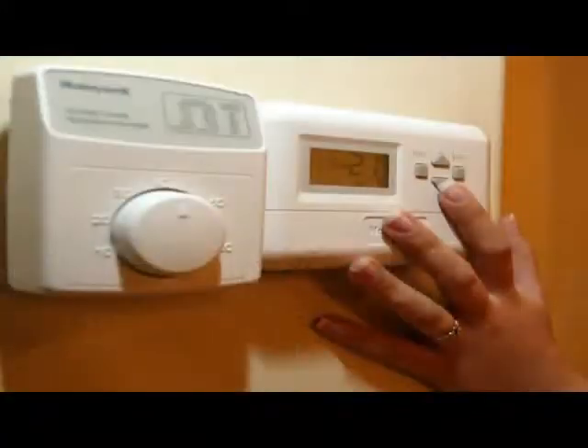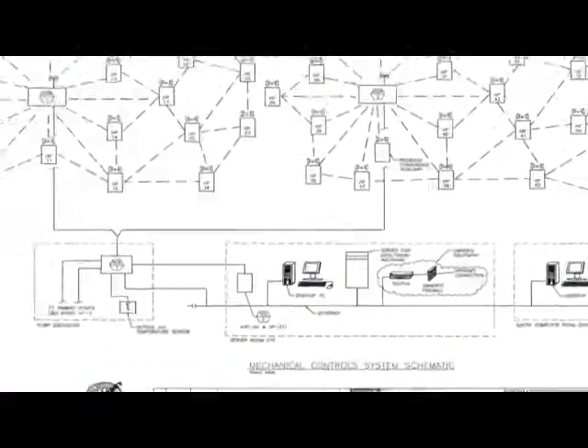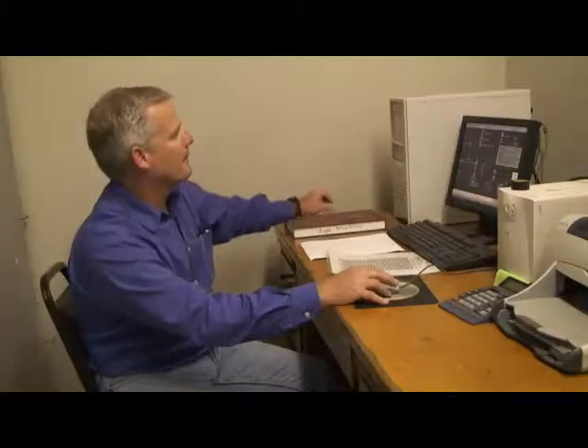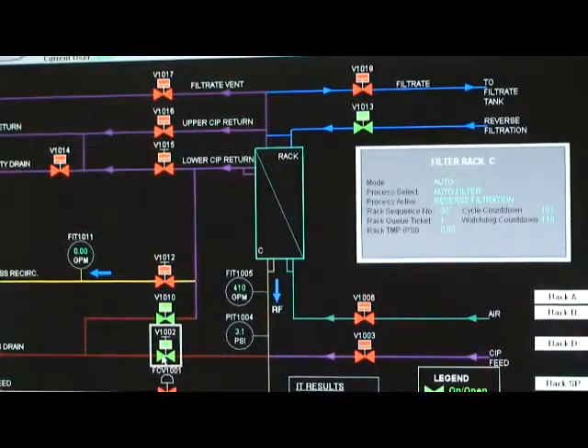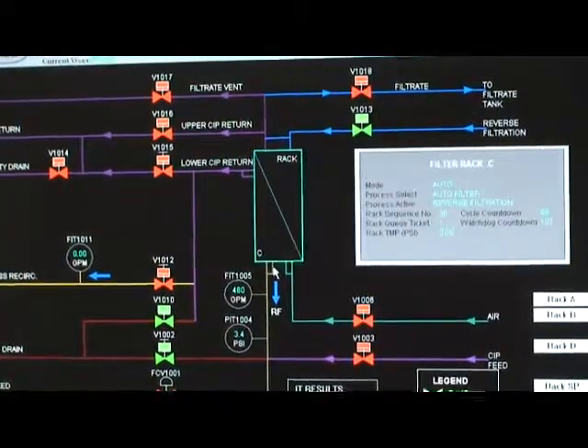Another benefit I particularly like is that the controls for these systems can be very simple. You just need a thermostat on the wall to control the heat pump, telling it when it should come on or off, and that's all there is to it. You don't have to measure pressure differences, temperature differences, and flow rates—it's on or it's off. That's not just easy for the users, but easy for the people who have to maintain those systems.